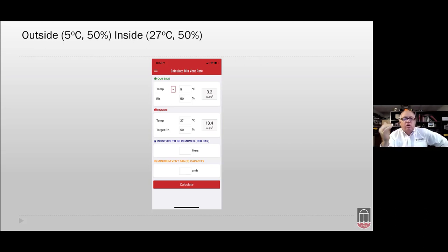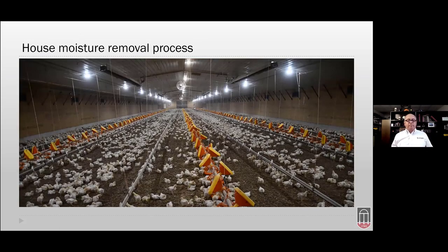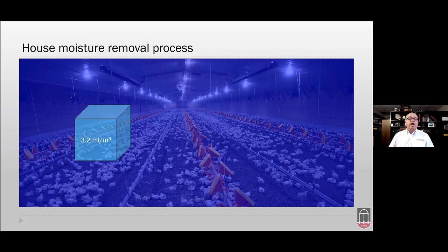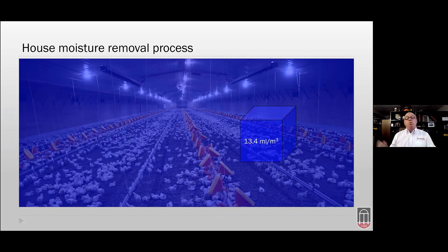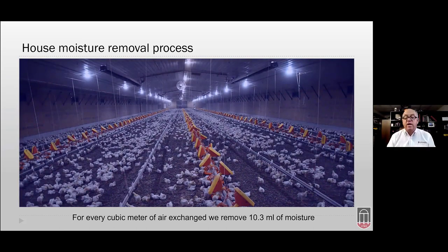Here's the moisture removal process: birds drinking 4,500 liters of water a day add moisture to air and litter. When we bring in one cubic meter of air, we bring in 3.2 milliliters of moisture, but we must exhaust one cubic meter as well — exhausting 13.4 milliliters. So for every cubic meter of air exchanged, we remove 10.3 milliliters of moisture.